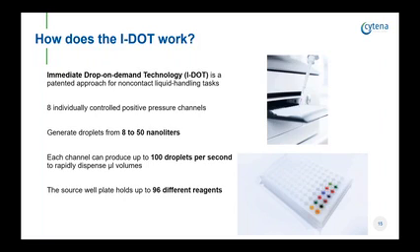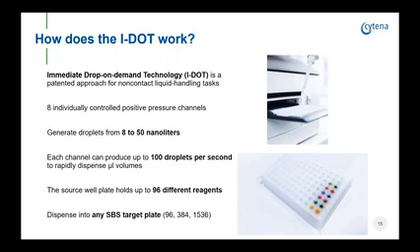What really sets the IDOT apart from other low volume liquid handlers is the disposable source well plate, which holds up to 96 different reagents. It looks like a normal 96-well plate that can be filled with standard pipettes, multi-channel pipettes, or even liquid handling robots. The system can dispense from any of these 96 wells into any well of a target plate, allowing even the most complex liquid handling tasks. It is compatible with standard plate formats such as 96, 384, or even 1536-well plates.